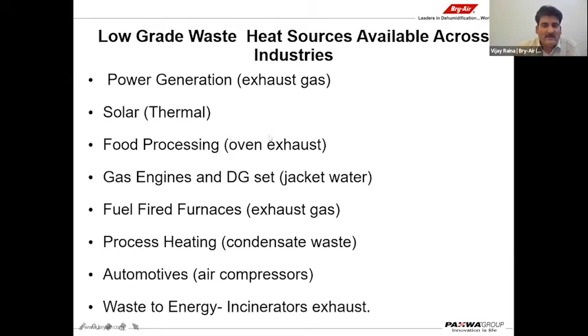Now we are also working on one development for screw or ammonia chiller condenser cooling. Wherever hot water is available from the superheater on the condenser side, that temperature generally goes to 55 to 60 degrees centigrade. That 60 we can easily use in our adsorption chiller, and we can generate chilled water for customers instead of using it in heating applications for washing, cleaning and so on. So this is another energy saving for the customer from existing screw chillers or ammonia chillers, like in the pneumatic air compressor, where we have this waste heat potential available.